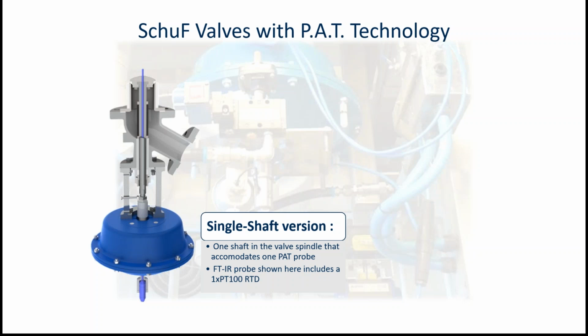On this first slide, you see our standard disc bottom outlet valve, a cross-section of it, and the single shaft version with the FT-IR probe, the blue piece on the bottom, going all the way through the shaft of the spindle and through the disc at the top, making direct contact with the process medium.